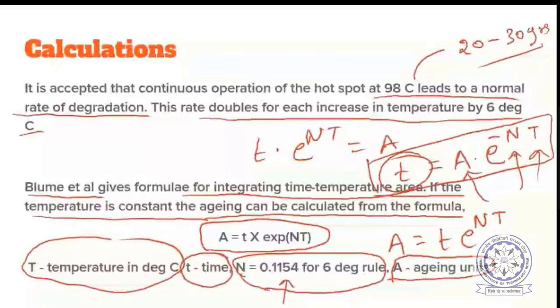Of course, the constant A, or even n, can be calculated from given data. Suppose I give that this much temperature for this much time causes aging units of this much, then based on that you can get the constants and use the same for the estimation of the life. For example, assuming a 6 degree rise leads to a rate of aging that is double, you can estimate the value of n. Like that, this formula can be used for estimating the life under any given temperature conditions.